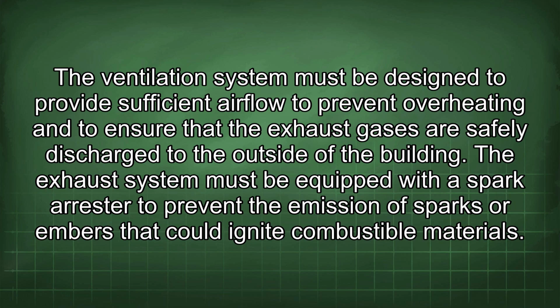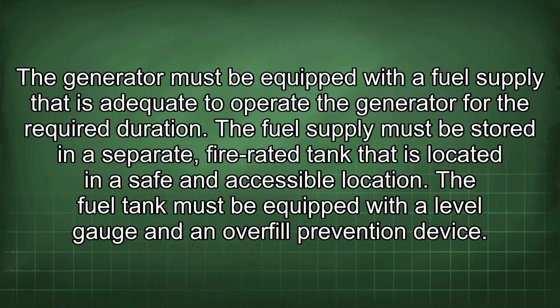The exhaust system must be equipped with a spark arrestor to prevent the emission of sparks or embers that could ignite combustible materials. The generator must be equipped with a fuel supply that is adequate to operate the generator for the required duration. The fuel supply must be stored in a separate, fire-rated tank that is located in a safe and accessible location. The fuel tank must be equipped with a level gauge and an overfill prevention device.